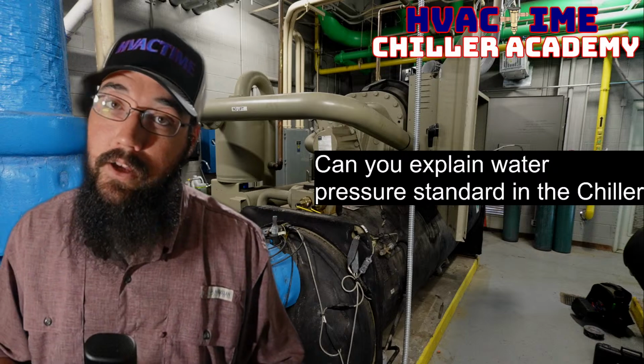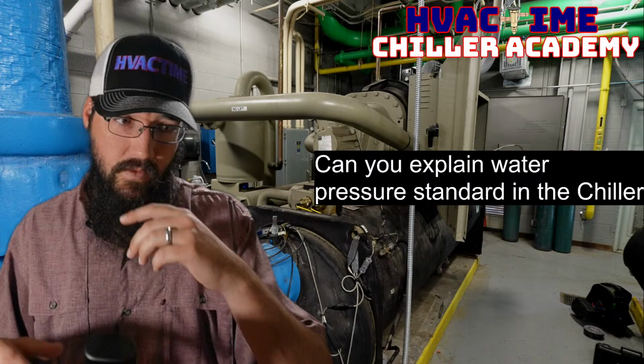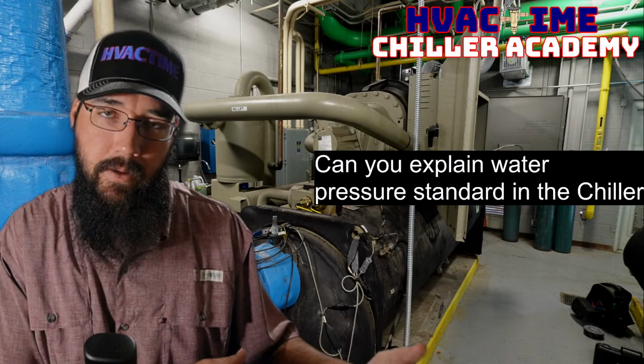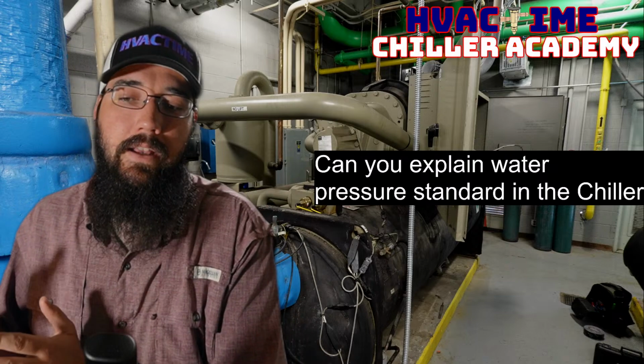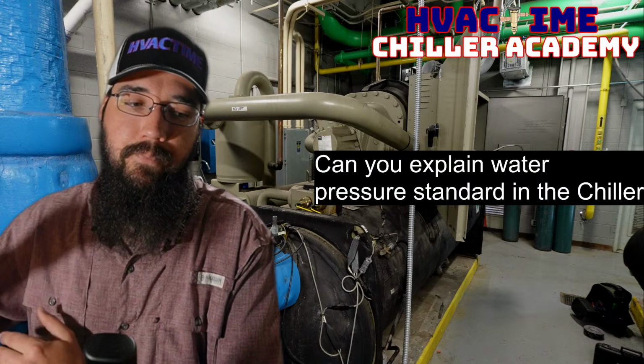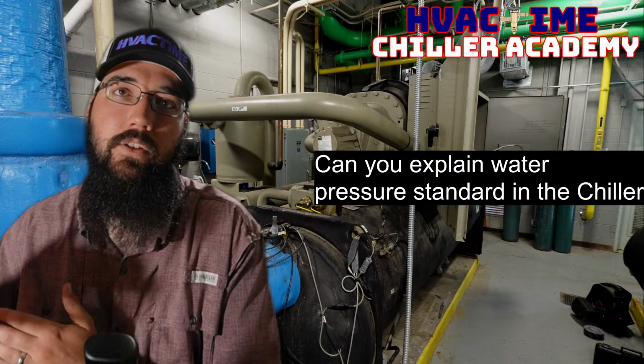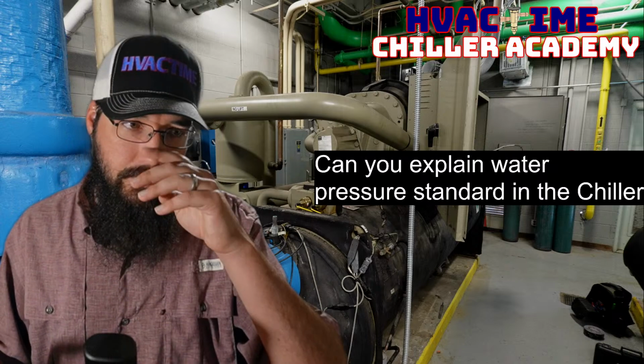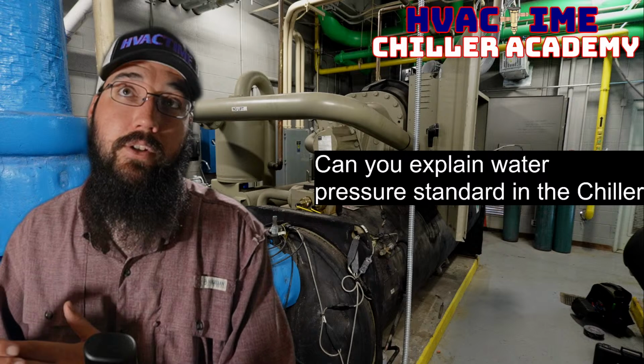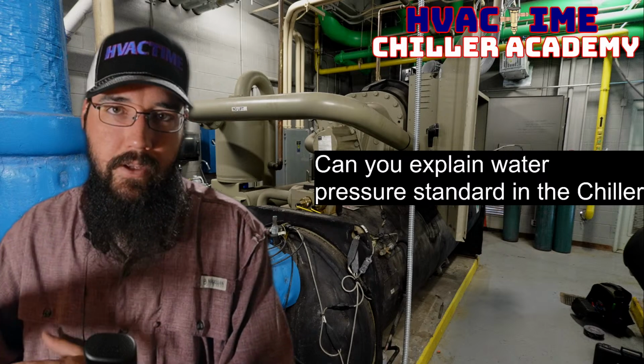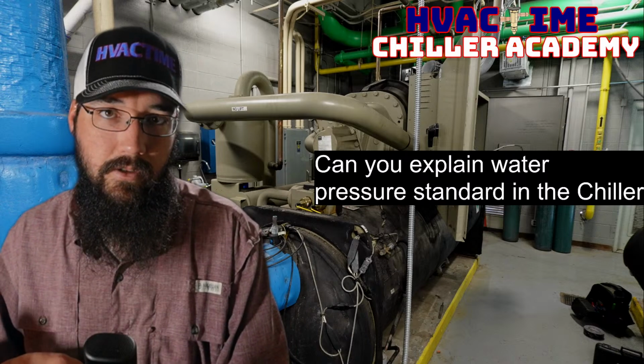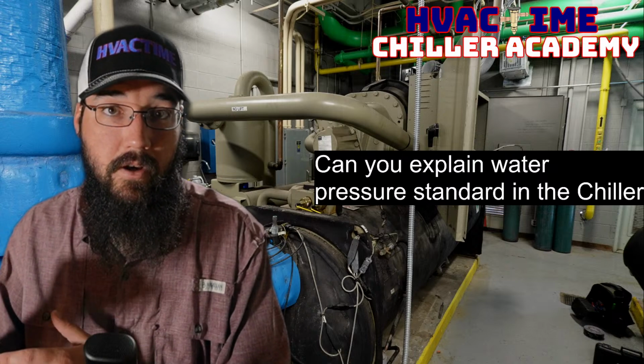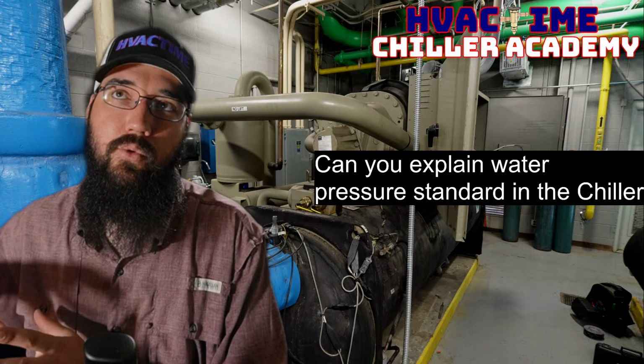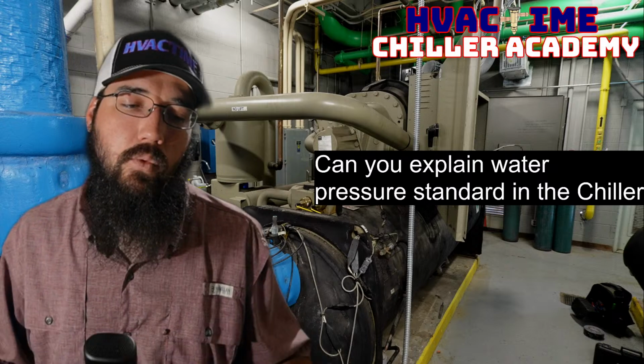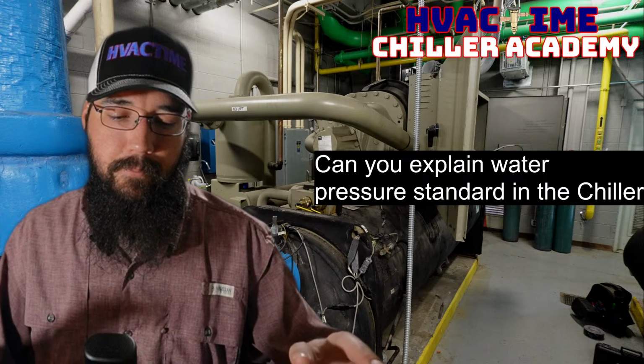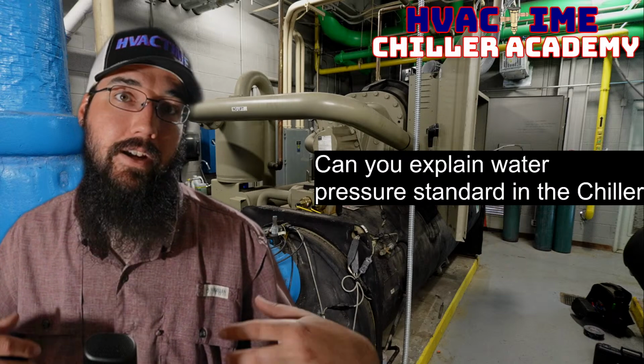Now that could be in the IOM, that could be in the engineering manuals. Most of these chillers will have an operations and maintenance manual, the IOM, and then a separate engineering manual. Those are the manuals they use to actually design and spec machines with customers. So if you're trying to determine what your flow is, you may be able to go in there, find that model using the digits in the model number, and then reference what your flow should be. Now, one of the issues with that is not all of those are going to be accurate, or they're not going to give you an actual DP value.